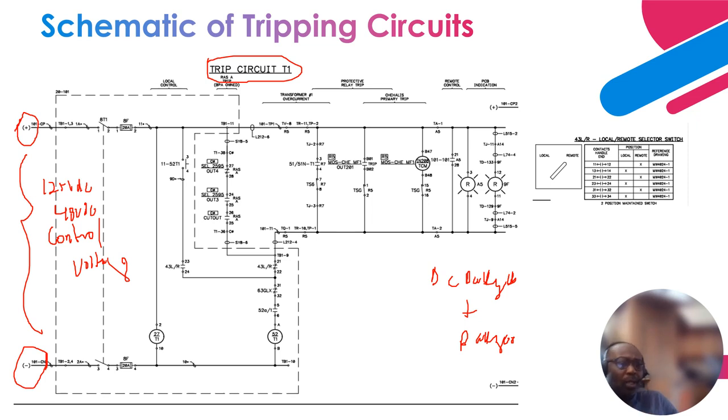that has many cells put together to achieve the required DC control voltage. Okay, so inside the circuit breaker, it's this fuse that disconnects, right? So this is what you see over here. It's a fuse that disconnects, and that is what you see inside the circuit breaker control panel or control cubicle. Many a time, if you are testing the breaker, operating open and close, that is what you operate to energize, to integrate it to the control voltage. As you can see over here, this is a local control.